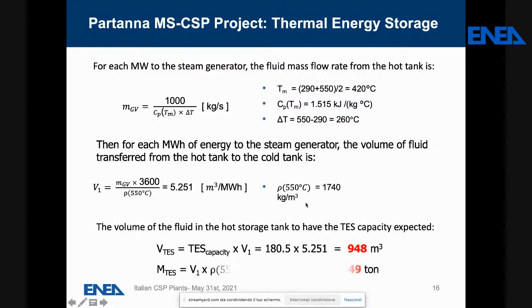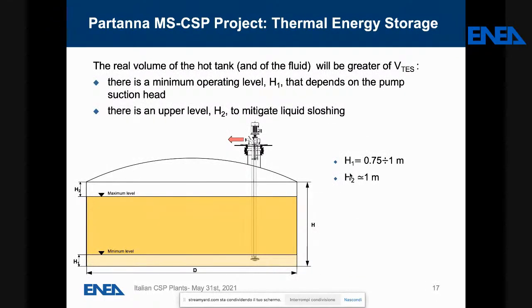With these two parameters, we can evaluate the total volume of the TES in cubic meters, and then the mass of the TES in tons. But we have to remember that this is the usable volume, because the final volume of the tank must be larger: there is a minimum operating level that depends on the pump suction head at the bottom of the tank, and there is also an upper level in order to mitigate the liquid sloshing. So the total volume of the tank will be greater than the value calculated with the previous data.